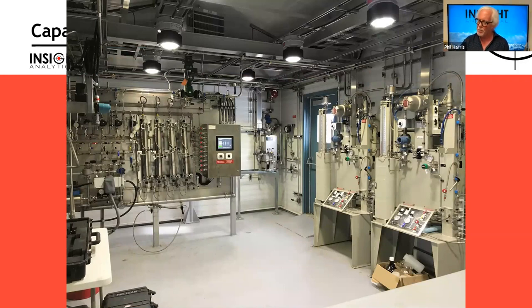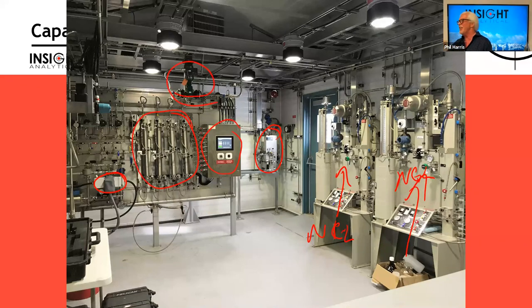There's a lot of our products in this building. Composite samplers. So this is a natural gas liquids system, with two composite samplers. These are pipeline measurements, every month filling up with a sample. Automated solvent flushes: a lot of times in sample systems, especially if they're waxy or dirty, the system starts to plug off, and you don't always have a technician there who can clean it. So we've automated back flush systems to solvent flush. As soon as we see, for example, on an optical analyzer, like the JP3 analyzer over here, transmission going down, the cell getting dirty, the system automatically flushes and cleans it. Full PLC, controlling automated grab sampling, controlling a control valve, so we have an isokinetic fast loop. Again, we love these kinds of projects.